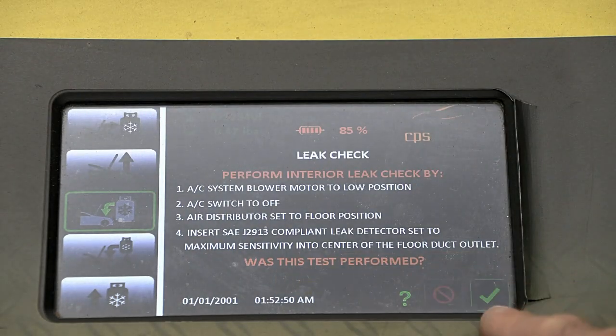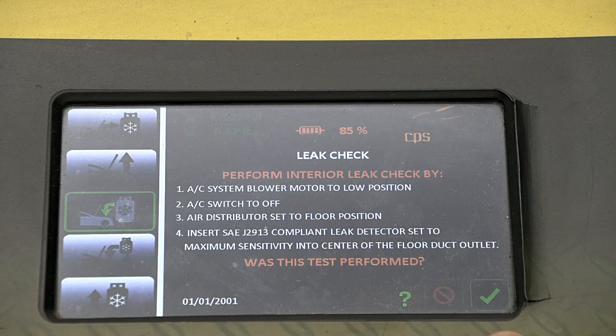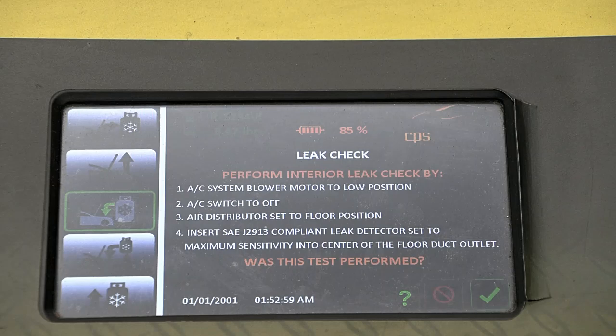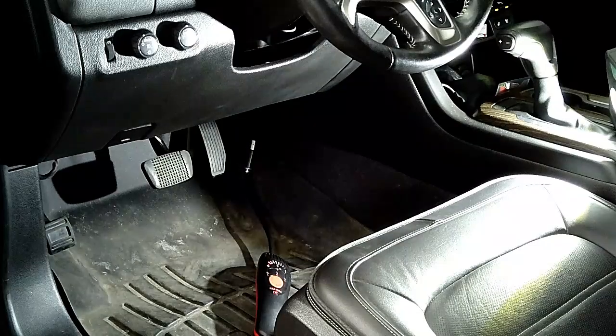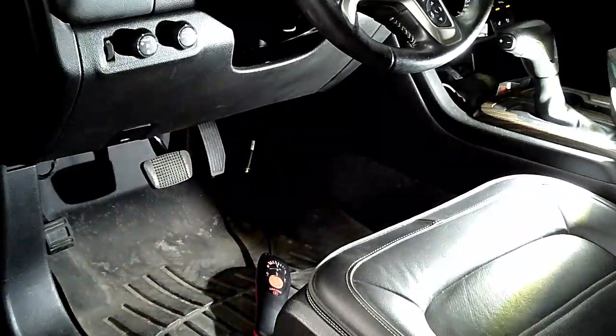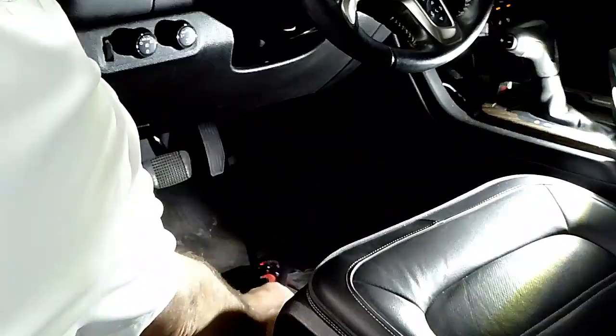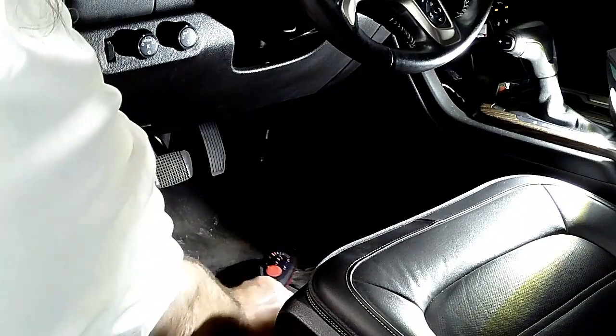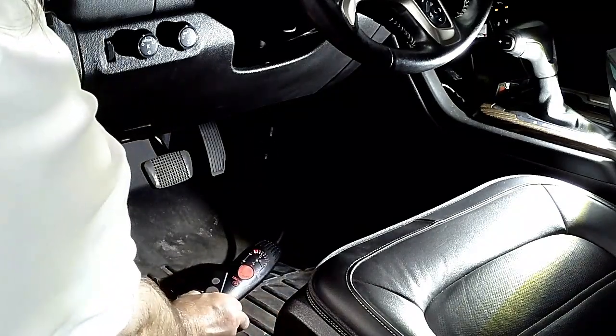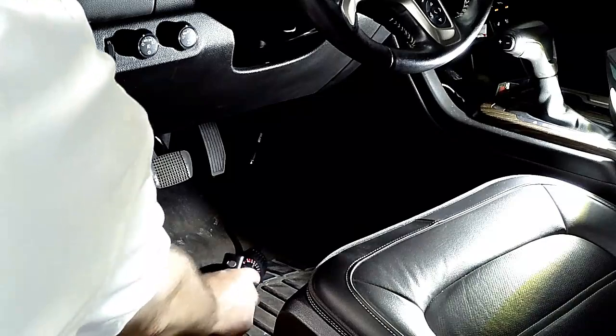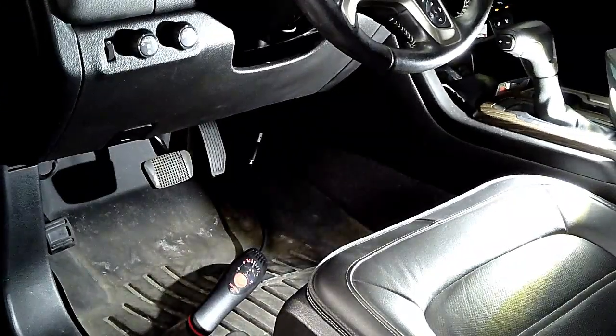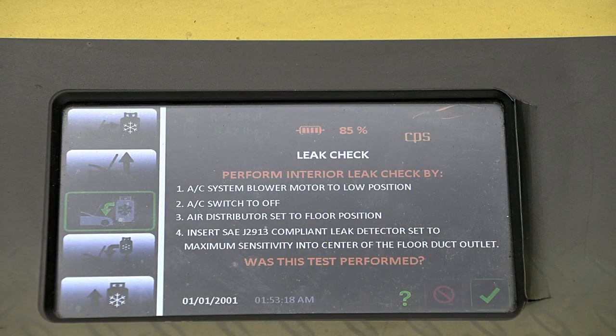And it says, was this test performed? Now, we got to cheat here because of the amount of time, right? So, yes, the test, you could hear it beeping. Now, that right here means we don't have a leak. You can see the light is only on one, okay? Could they see that pretty good? Okay. So we're on the highest sensitivity on low. We don't have a leak. That's 15% of the charge. We're going to say yes.